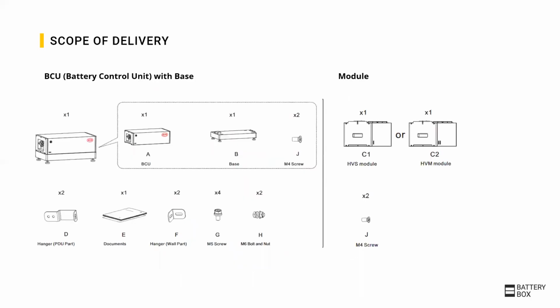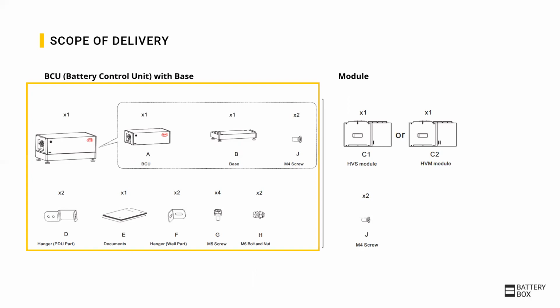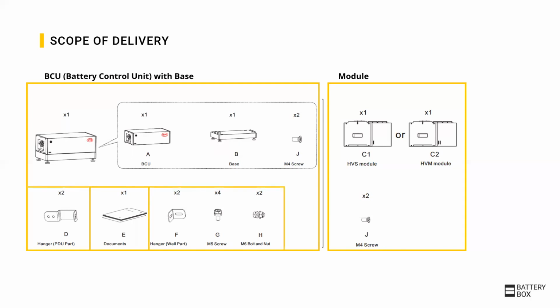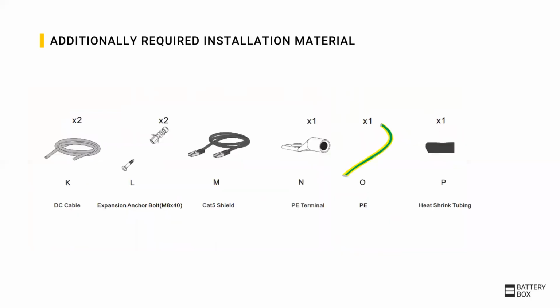For the installation, you need 2 parts and packages of the battery box: the base and the BCU, which is a battery control unit, and the modules. In the package with the BCU and base, you will find some documents, as well as the parts for the wall mounting. In the module package, you will find the module and the screws to fix the modules on top of each other. For the installation, you will additionally need, per battery box tower, the DC cables, the screws and bolt for the wall fixation, the communication cable with cat 5 or higher, and the ground cable.